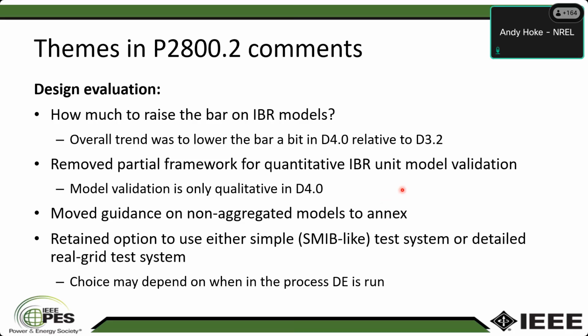I would say the overall trend going from draft 3.2 to draft 4 was to actually lower the bar just a little bit. For example, we took out quantitative IBR unit model validation. In other words, is it plus or minus 5% when you're trying to match a simulation trace to a model, to a hardware test trace, or is it some other number? We had a framework for that. That's actually gone now. Now it's all left up to qualitative. Basically, just an engineer looks at the traces and says, looks good to me. It is the paradigm there.